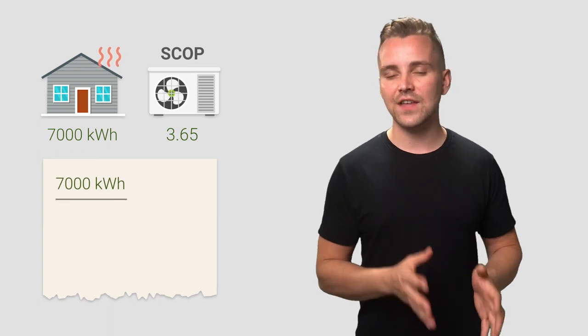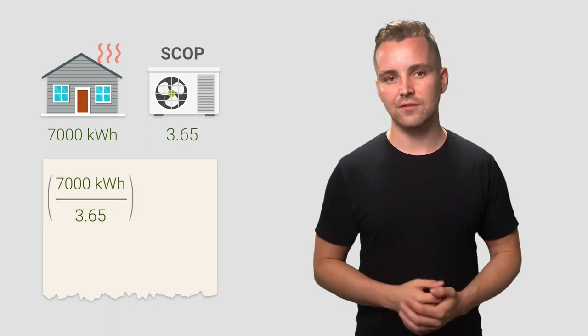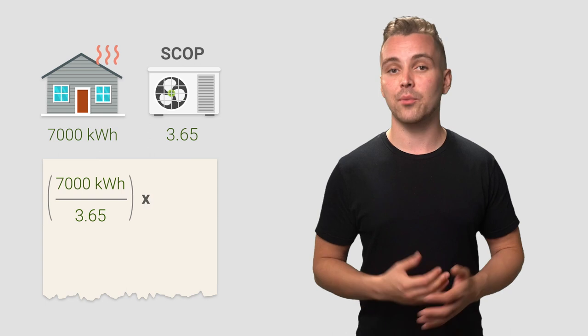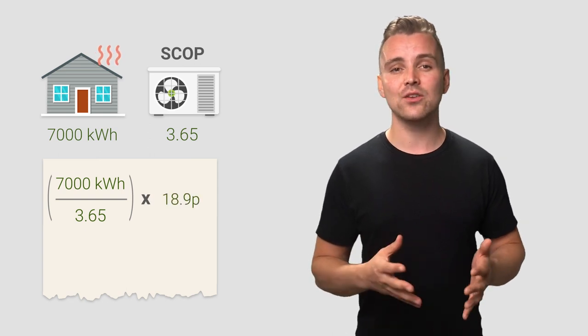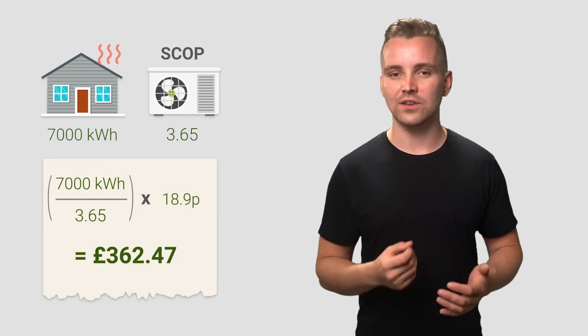For example, a small apartment or flat has an average annual heat requirement of 7,000 kilowatt hours. The average seasonal coefficient of performance for a heat pump in a property of this size is 3.65. So we divide 7,000 by 3.65 and then multiply it by 18.9p, giving us an annual running cost of £362.47.